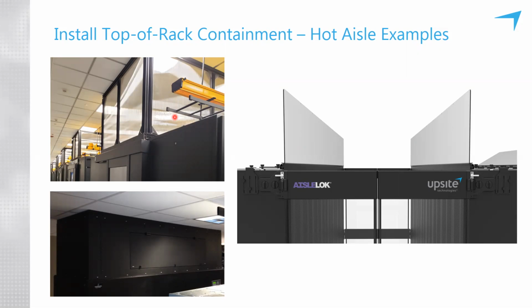And I would just add that if you don't have a ceiling return plenum, but you do have a high ceiling in the room, hot aisle containment could still be an option for you. In which case you would raise the top of the hot aisle off the racks, all the way up to where the jurisdiction says you have to remain X amount of inches, usually 18, from a sprinkler head, and stop it there. And you do the same for the air conditioning unit. You would raise that intake up. You just wouldn't be coupling it to a drop ceiling. You would raise it up, and that increases the delta T. You're going to be returning a lot warmer air to the air conditioning unit. And when Lars talks about the science and the delta Ts later on, you'll understand why that's important.